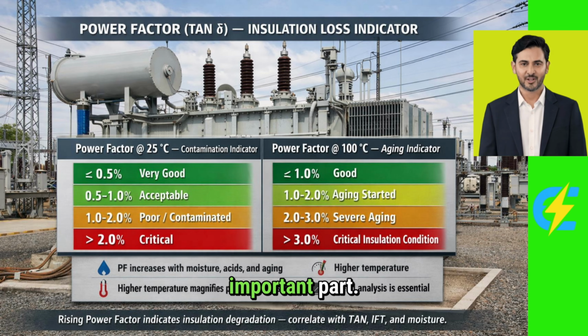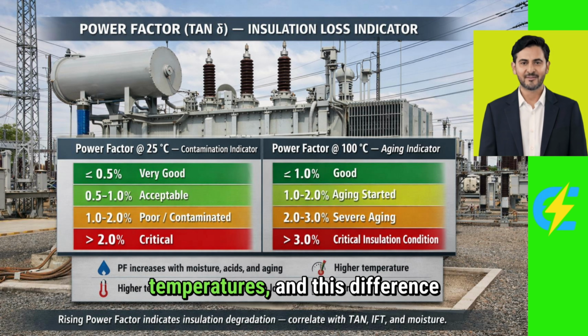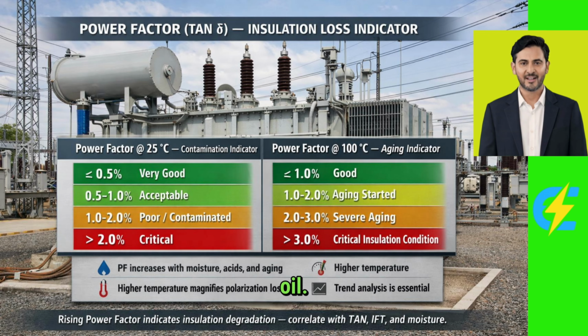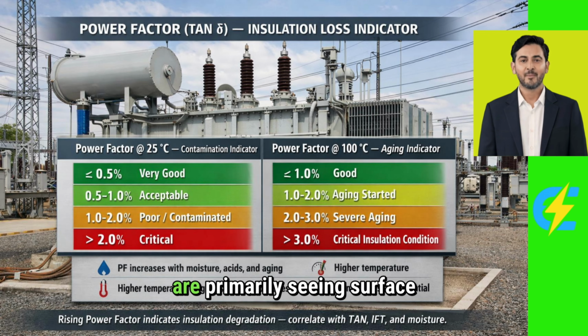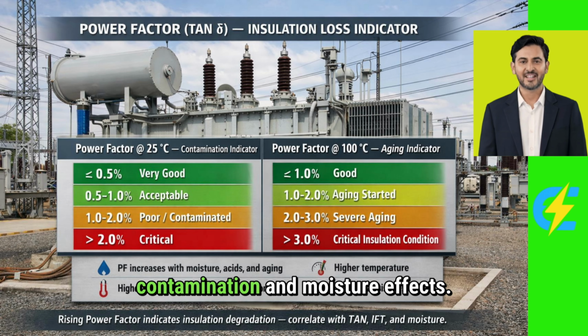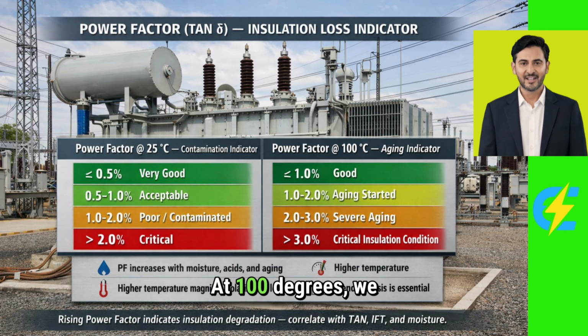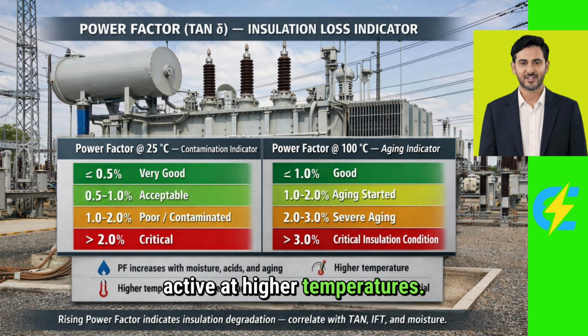Now here's the most important part. Why do we test at both 25 degrees and 100 degrees Celsius? The oil behaves completely differently at these 2 temperatures. And this difference reveals crucial information about what's wrong with the oil. At 25 degrees, we are primarily seeing surface contamination and moisture effects. At 100 degrees, we are seeing deep chemical aging and polar oxidation products that only become active at higher temperatures. That's why both temperatures are mandatory for correct interpretation.